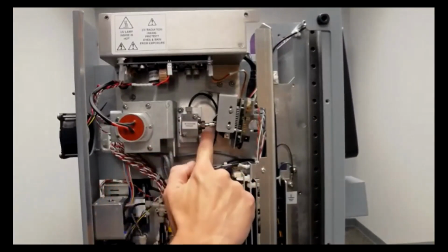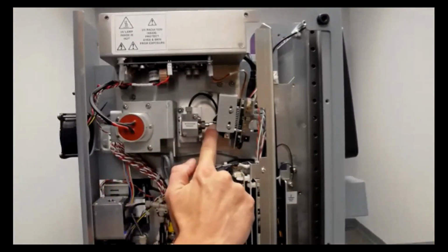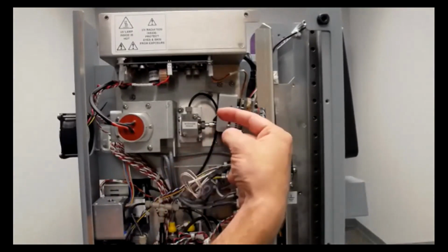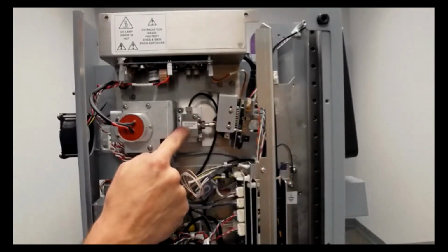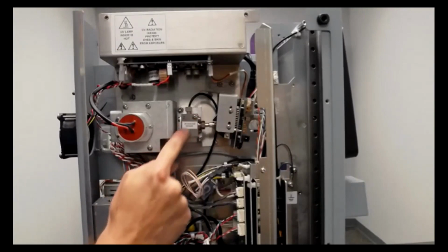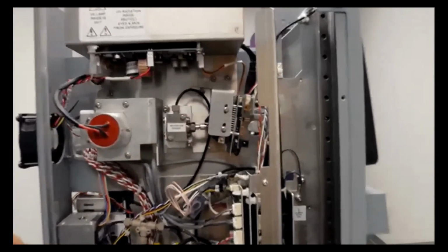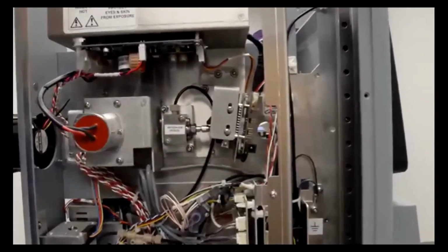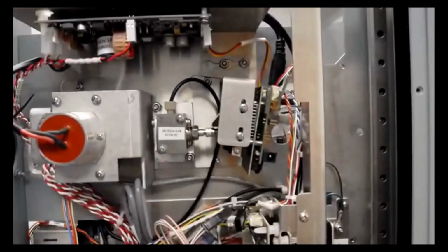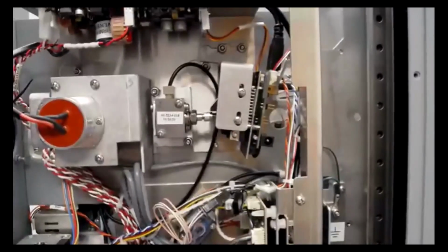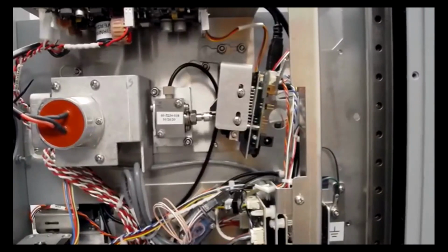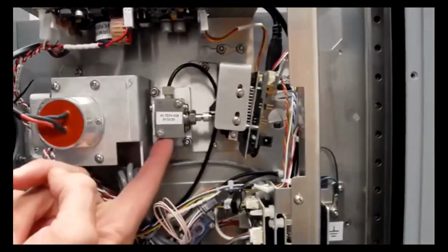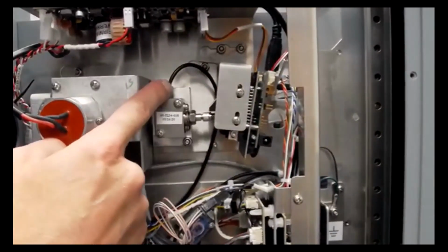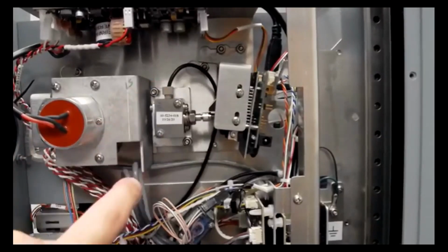Now, there's this rod, there's a fiber optic rod that comes from the detector and it goes into the flow cell. So you can't just remove the screws that mount the flow cell and rip it out, because something's gonna break. This is close as I can. All right, so actually the first thing you wanna do is remove the tubing lines. We already removed the bottom one, so I'm gonna get this top one taken off.